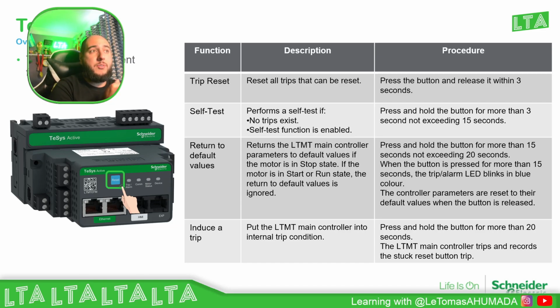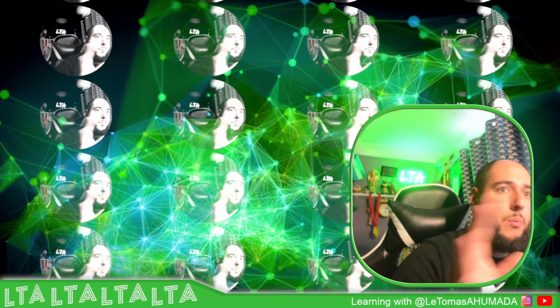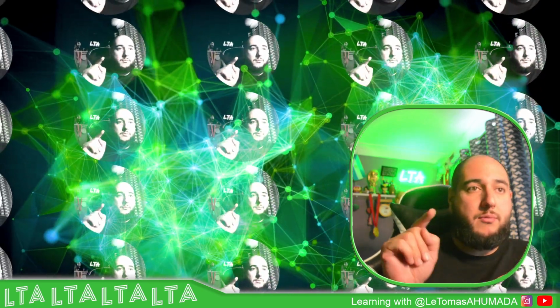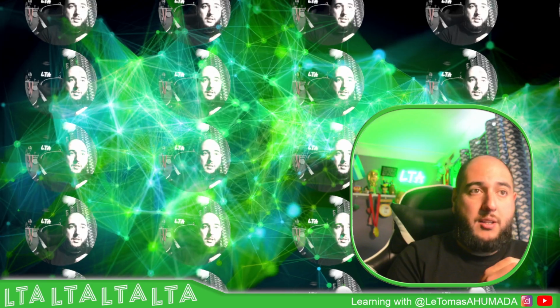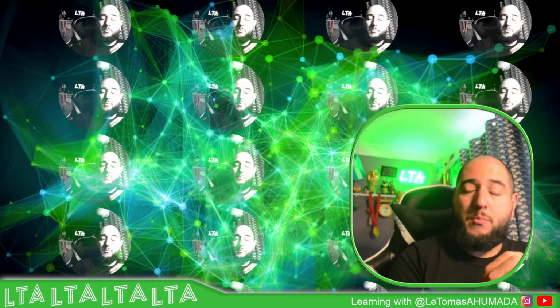I'm going to do a specific video on each of them so we can show you how this one works. So this is just an overview. Probably the main ones are going to be the reset trip and the factory reset. I use that often, and that one is important because if you don't know what is inside and you want to start from scratch, then factory reset it, wait until you have 15 seconds. That's going to be the flashing LED in blue, and then you should be able to release it and it will start again.